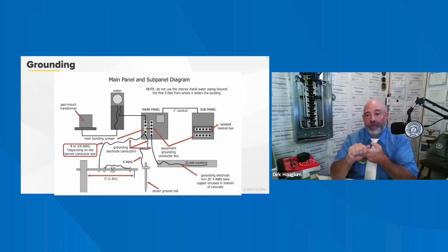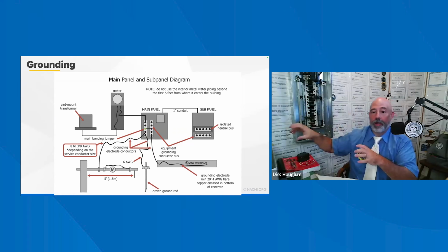The last stop on the utility distribution chain before the supply goes to the building is the transformer. This steps the high voltage primary distribution down in the neighborhood to the 240/120 volt feed to your house. On a typical 240/120 volt service drop, we have two ungrounded conductors and a single grounded conductor. This means you have to establish your own grounding electrode system at the house. Three grounding electrode conductors come from the main panel: one connects to the metal water pipe, another to the driven grounding rod, and the third to the copper wire inside the concrete.